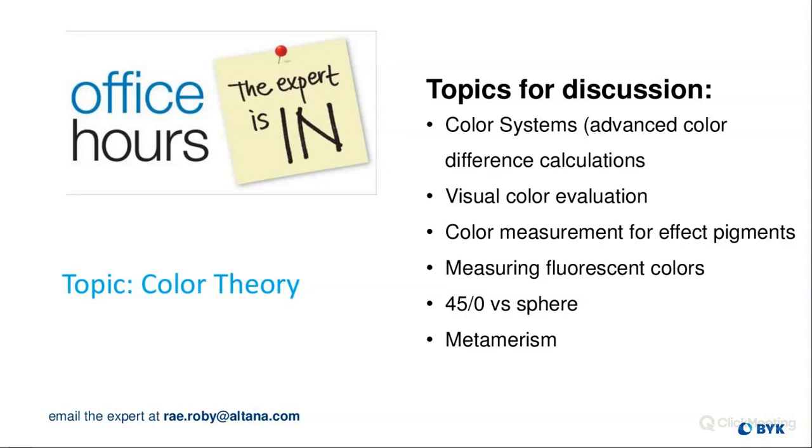So either you're not shipping parts that are technically within visual specification tolerance, or you're shipping things that are out of tolerance. So it's really important that you do set up for each individual color, depending on what color system you're using, and make sure that that's correct to what you see visually.